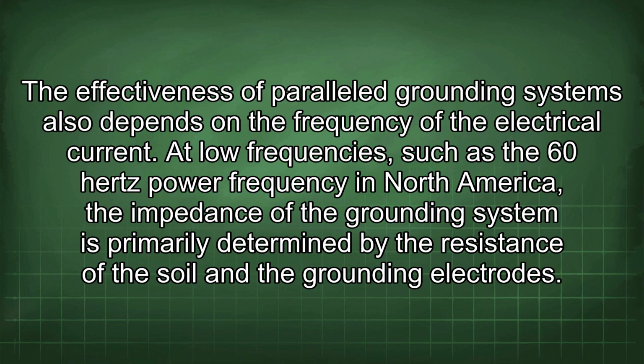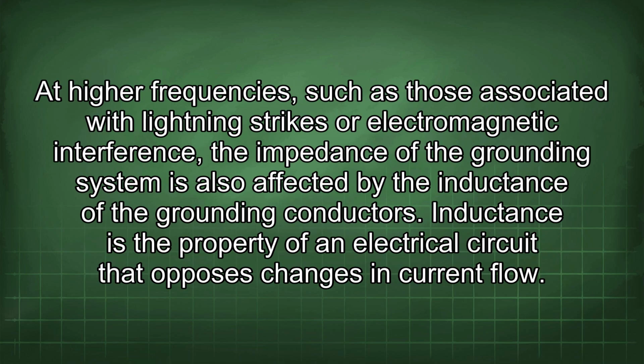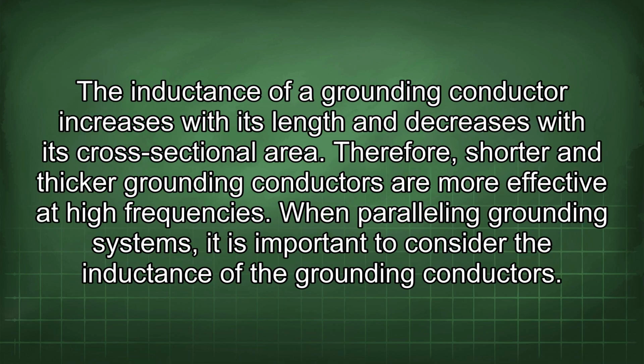The effectiveness of parallel grounding systems also depends on the frequency of the electrical current. At low frequencies, such as the 60 Hz power frequency in North America, the impedance of the grounding system is primarily determined by the resistance of the soil and the grounding electrodes. At high frequencies, such as those associated with lightning strikes or electromagnetic interference, the impedance of the grounding system is also affected by the inductance of the grounding conductors. Inductance is the property of an electrical circuit that opposes changes in current flow. The inductance of a grounding conductor increases with its length and decreases with its cross-sectional area. Therefore, shorter and thicker grounding conductors are more effective at high frequencies.